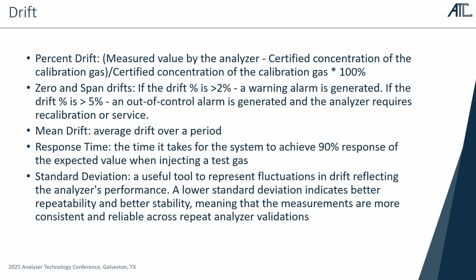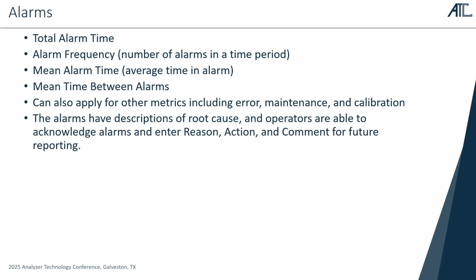And then this is where you would have the analysis, and then you need to service the system and see what's happening with it. Some of the alarm KPIs that were created: total alarm time, alarm frequency, mean time of alarm, like average time of alarm, and mean time between alarms. All these different KPIs can be used to further analyze the health of your CEMS and to see where you would need to investigate. And then you can generate reports and drill down on any specific analyzer or any specific time period.